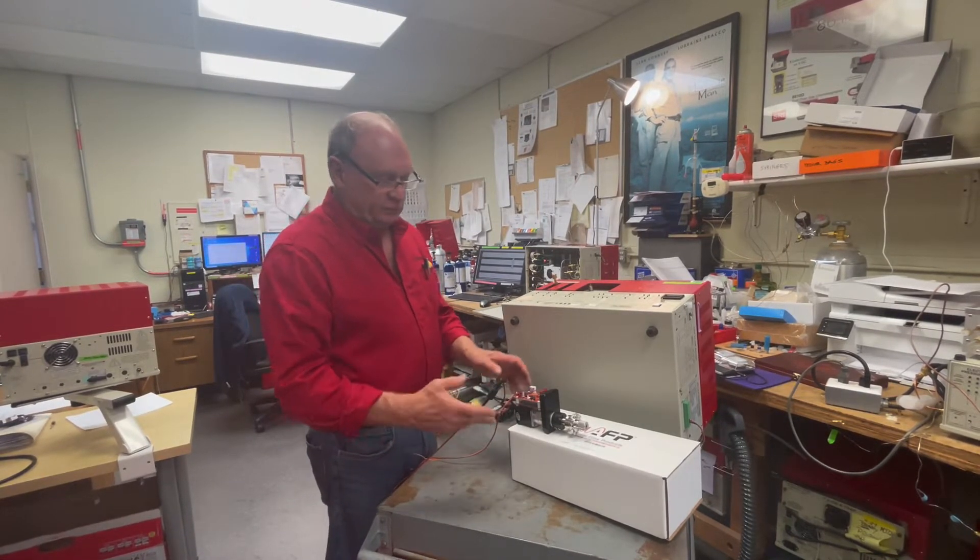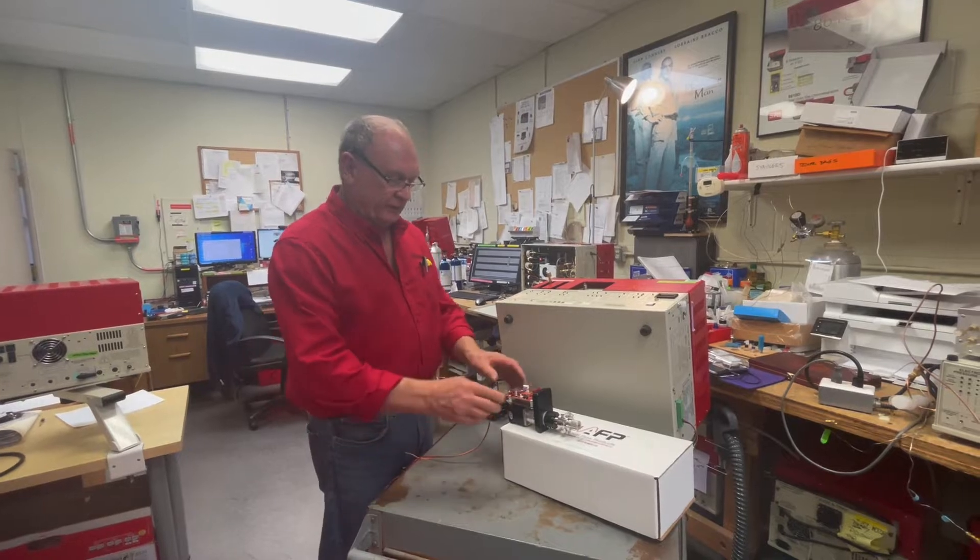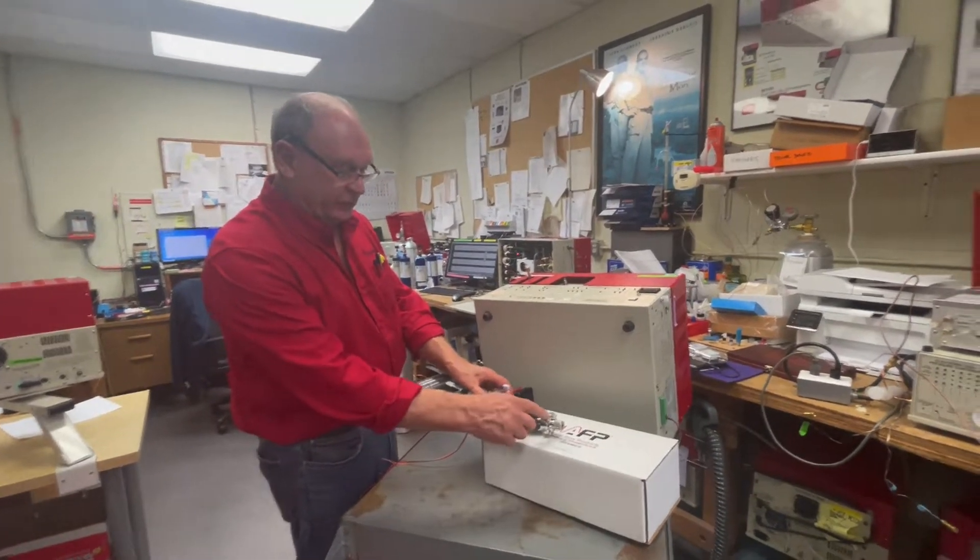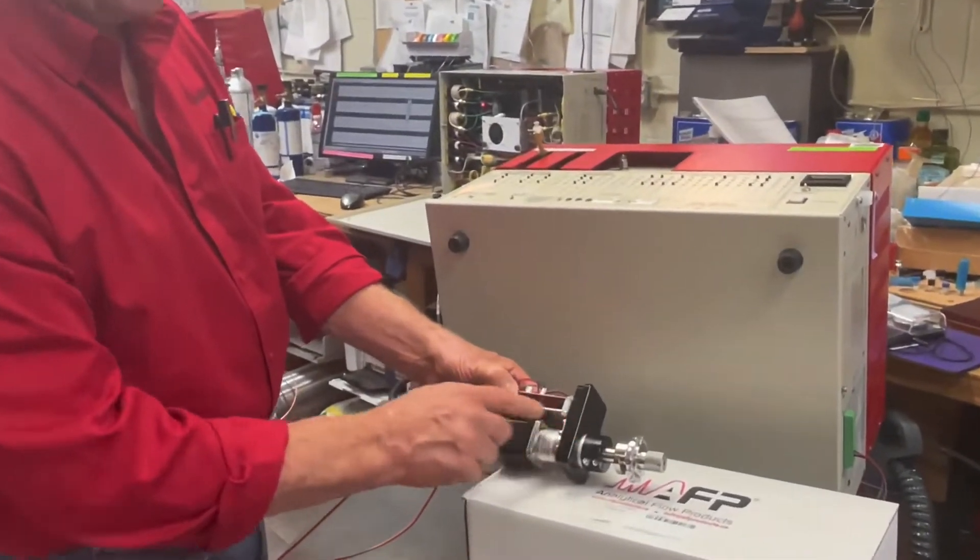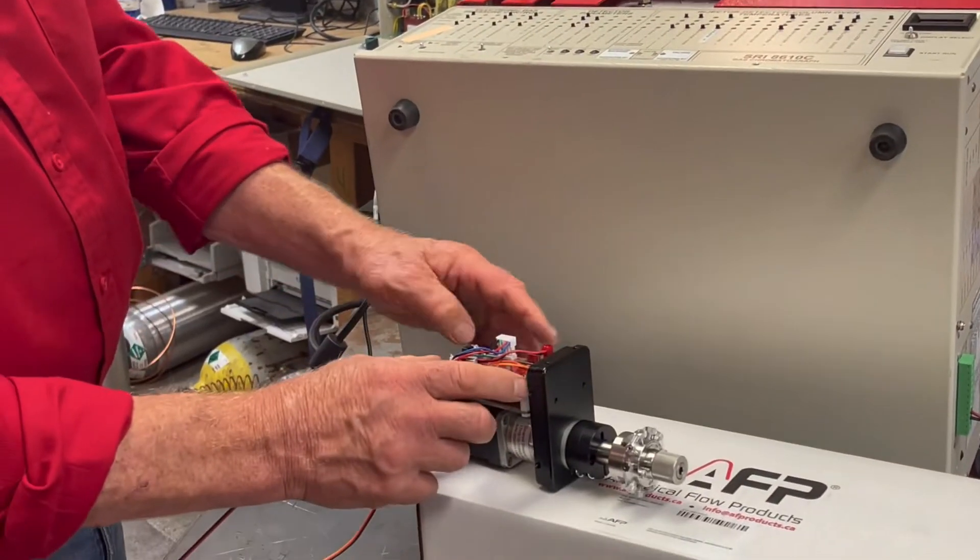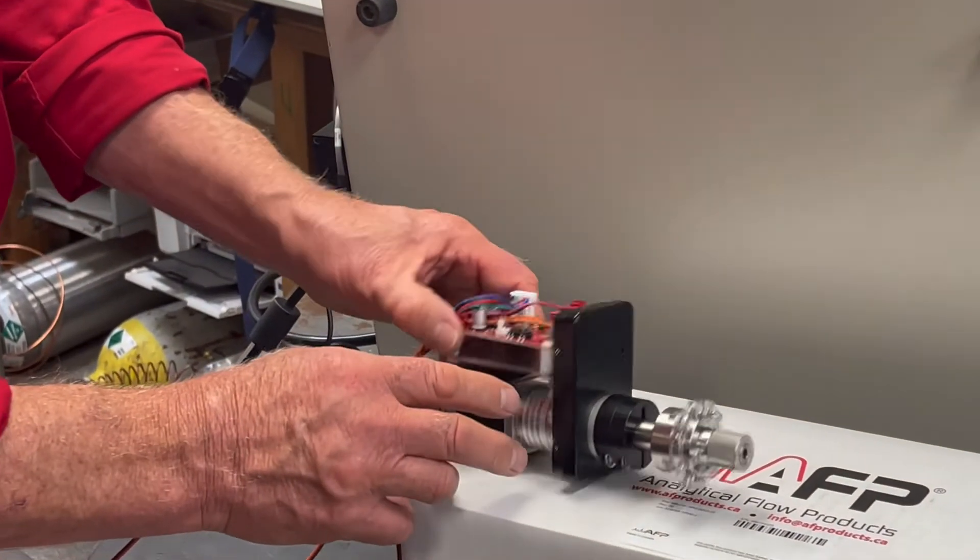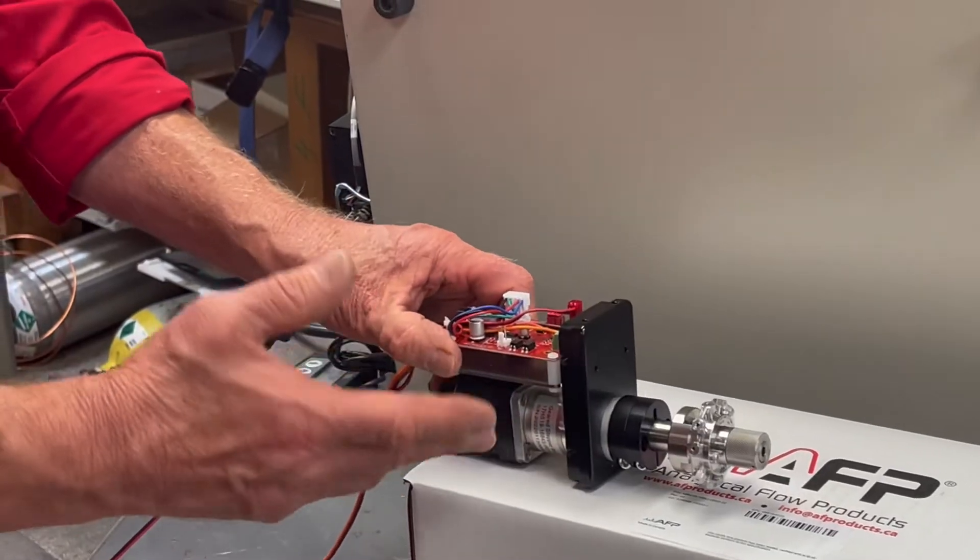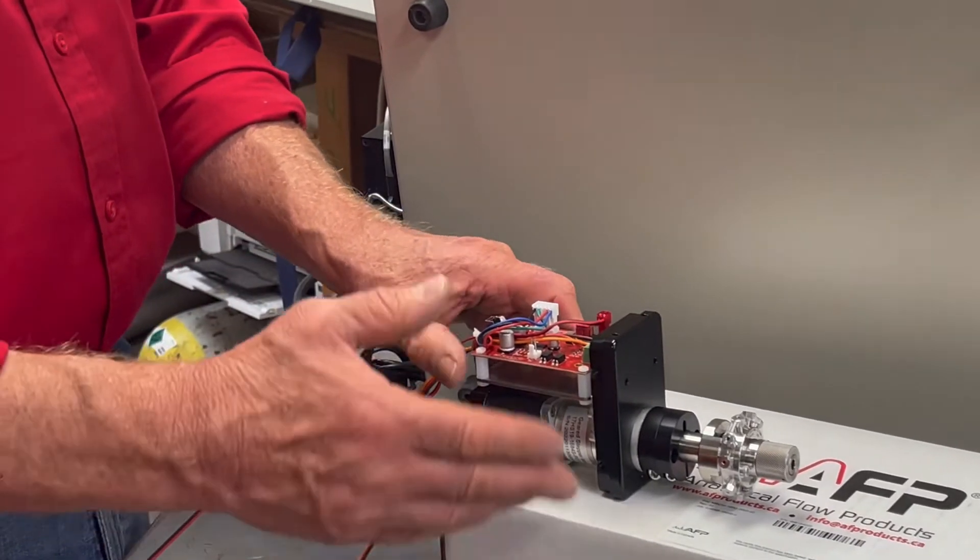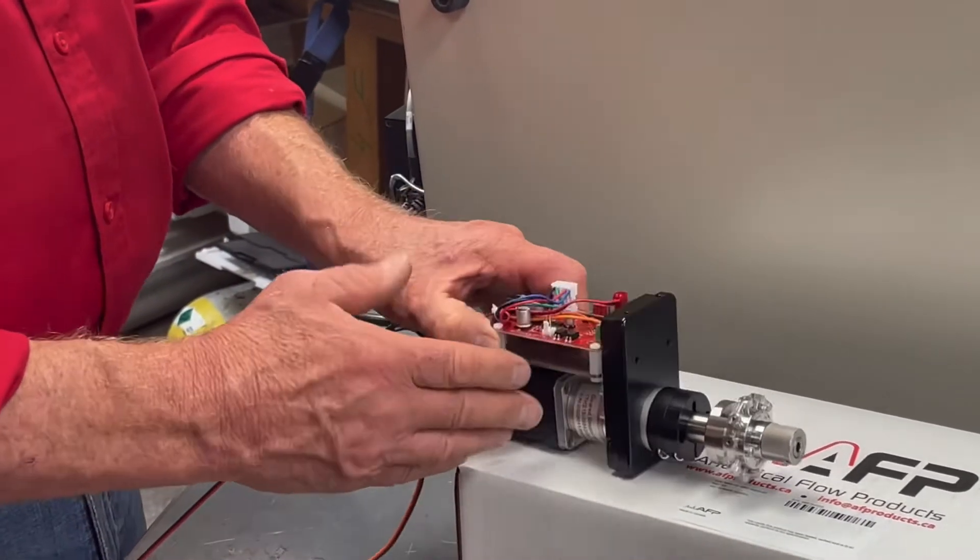In the old days, this really wasn't necessary because the actuator, the thing that turns the gas sampling valve, this is called an actuator, it's a motor and something to control the motor. These kind of motors are called stepper motors. The older motors were different, they only did one thing, but these can be told to do a million things.